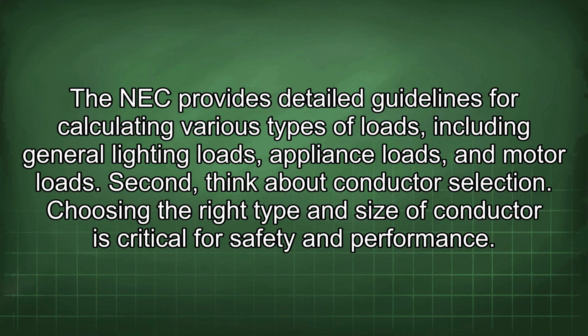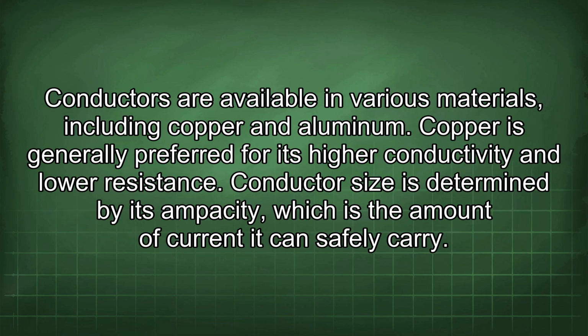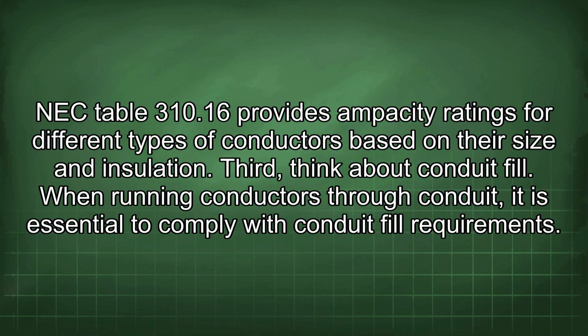Second, think about conductor selection. Choosing the right type and size of conductor is critical for safety and performance. Conductors are available in various materials, including copper and aluminum. Copper is generally preferred for its higher conductivity and lower resistance. Conductor size is determined by its ampacity, which is the amount of current it can safely carry. NEC Table 310.16 provides ampacity ratings for different types of conductors based on their size and insulation.